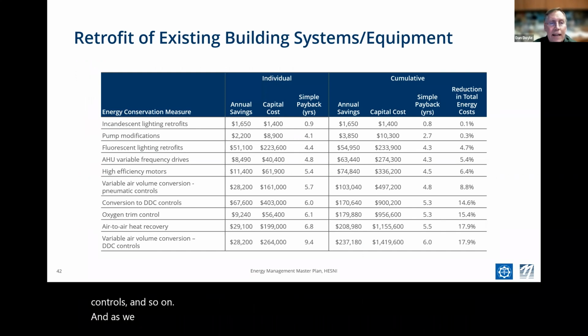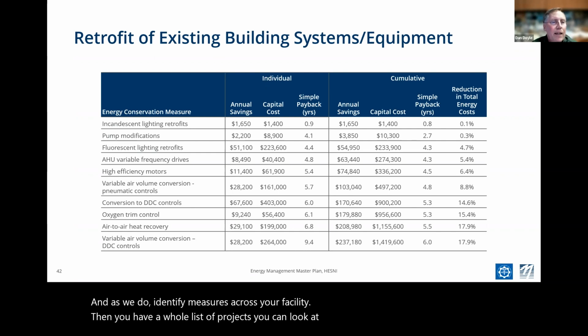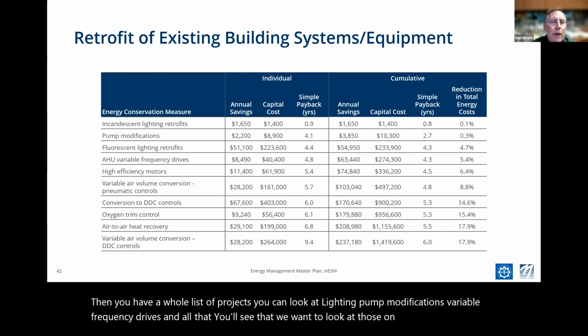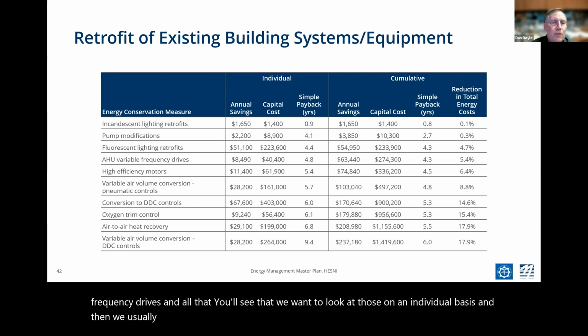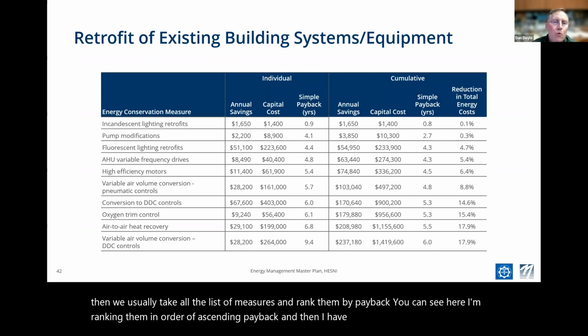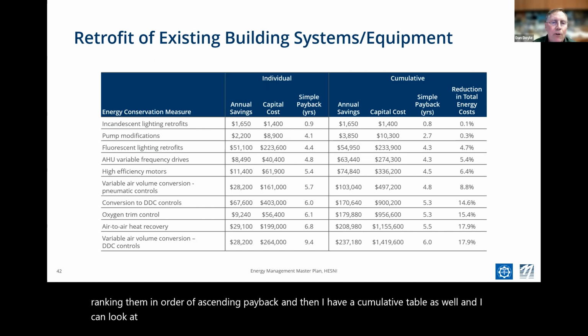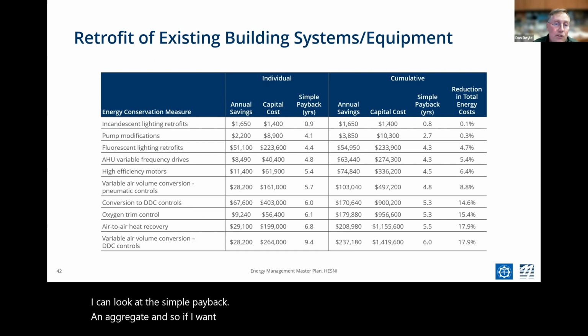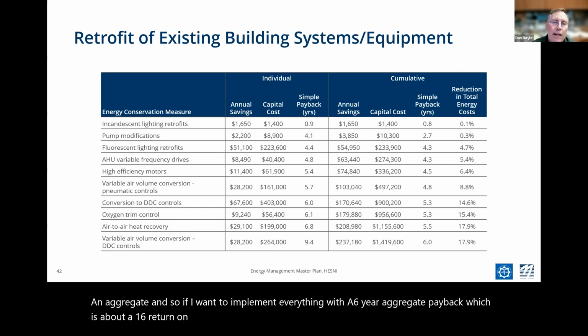And as we do identify measures across your facility, and you have a whole list of projects you can look at, lighting, pump modifications, variable frequency drives and all that, you'll see that we want to look at those on an individual basis. And then we usually take all the list of measures and rank them by payback. You can see here I'm ranking them in order of ascending payback. And then I have a cumulative table as well. And I can look at the simple payback in aggregate. And so if I want to implement everything with, say, a 6-year aggregate payback, which is about a 16% return on investment, I can get about an 18% reduction in our energy use and costs on that site.